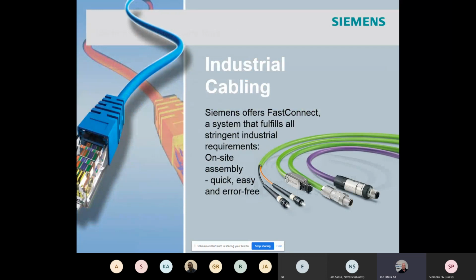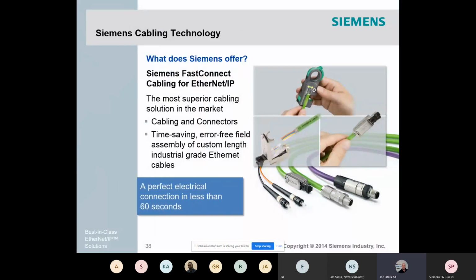Siemens offers industrial cabling as well. Siemens cables are not required for any application. Customers can choose their own cables, obviously. Siemens has stripping tools that cut the conductors and shield to the right length so that when you're using our connectors, customers will have an easy and reliable cable connection. Our RJ45 connector is metallic, not plastic, to maintain the ground and shield connections entirely, which is important in systems using servo controls or high noise areas. It connects to the switch frame, not the PC board, assuring better shock and vibration resistance and not damaging the PC board.